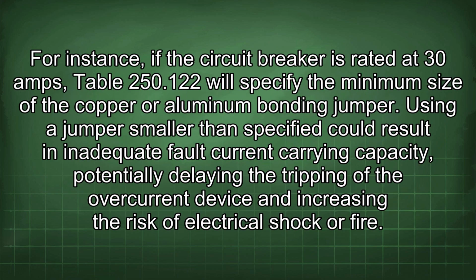For instance, if the circuit breaker is rated at 30 amps, Table 250.122 will specify the minimum size of the copper or aluminum bonding jumper. Using a jumper smaller than specified could result in inadequate fault current carrying capacity, potentially delaying the tripping of the overcurrent device and increasing the risk of electrical shock or fire.